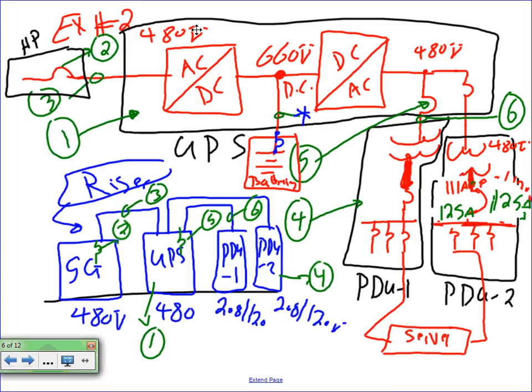These plugs will be underground. The multi-out assembly will be plugged into a receptacle under the floor, and that receptacle will be fed from PDU 1, that's circuit 1, and from PDU 2, circuit 2. So they have dual feeds to that server rack.